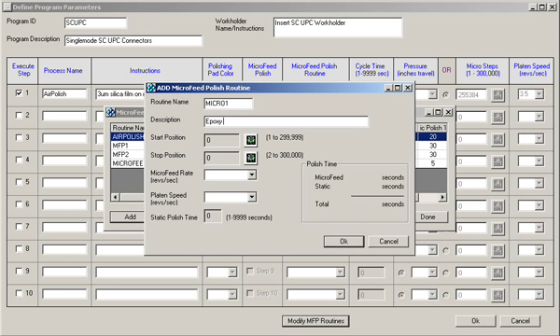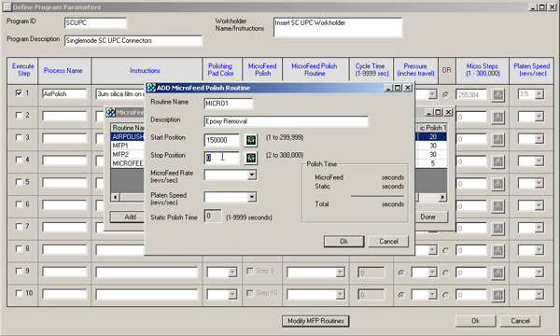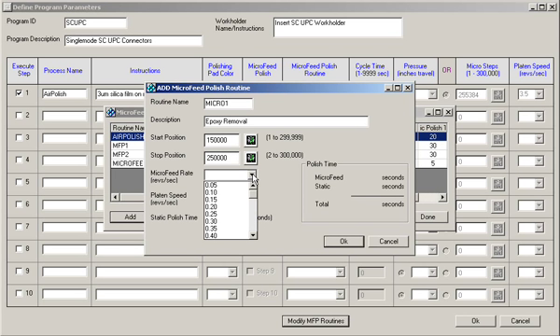Then, relative to the work holder's home position, a start and stop position are entered. After every polishing cycle, SEPTOR automatically returns the work holder to its home position. All distances are measured relative to the home position, which is factory set and cannot be changed. Note that teach utilities are also available for determining positioning.